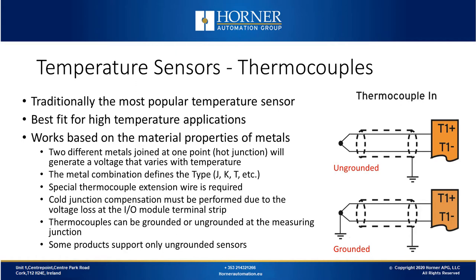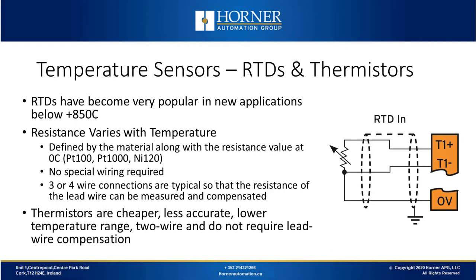A further complication is that thermocouples might be either grounded or ungrounded at the tip. Some IO modules will only support ungrounded sensors, while others will support both. RTDs are very cost effective and can be used at temperature ranges between minus 200 degrees Celsius and plus 800 degrees Celsius. Their resistance varies with temperature. They're typically named based on their material and resistance value at zero degrees — so a PT100 is a platinum resistor where the resistance value is 100 ohms at zero Celsius. You do need to connect at least three wires to the sensor so the resistance of the lead wire can be measured and compensated.